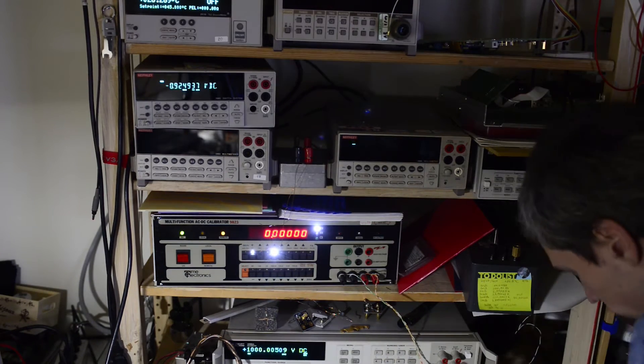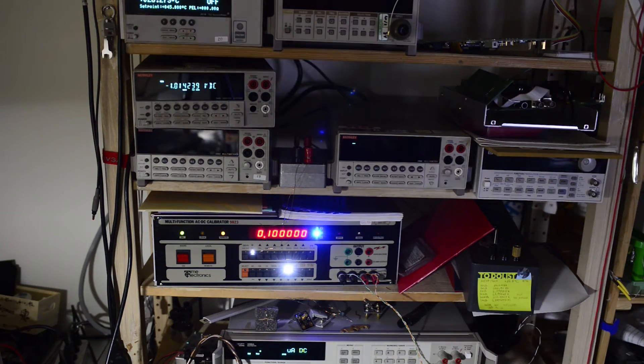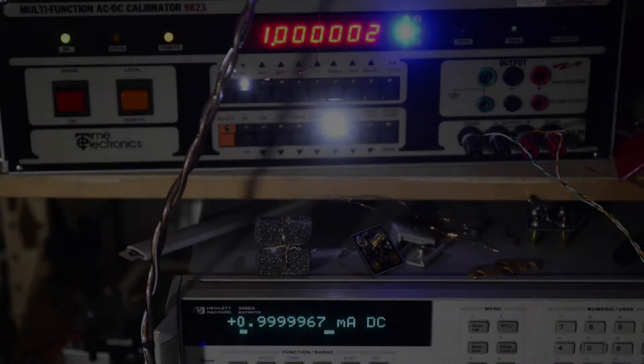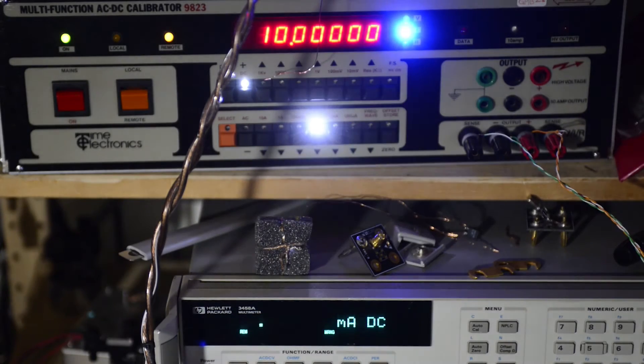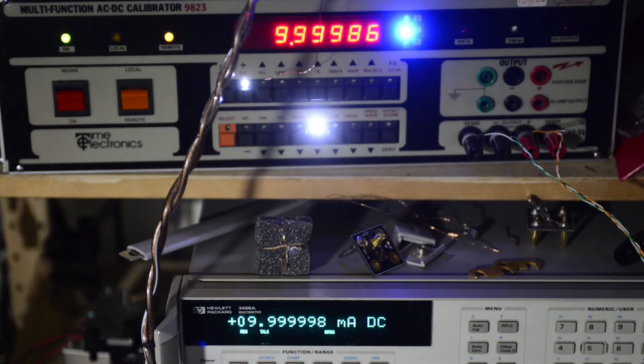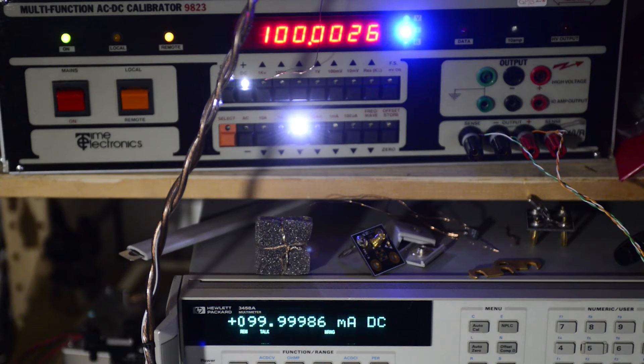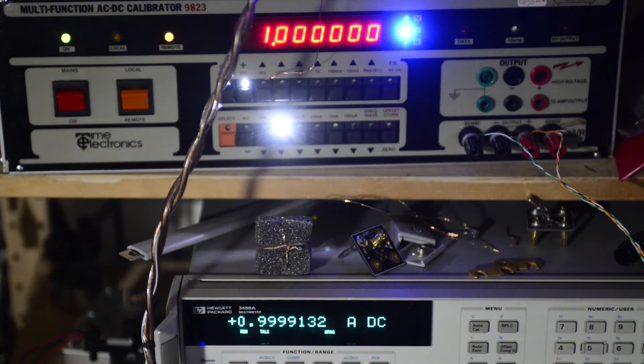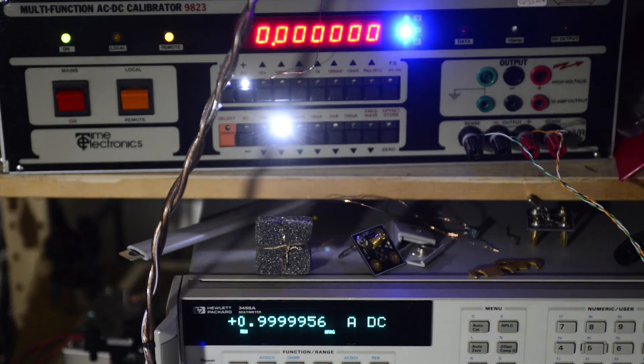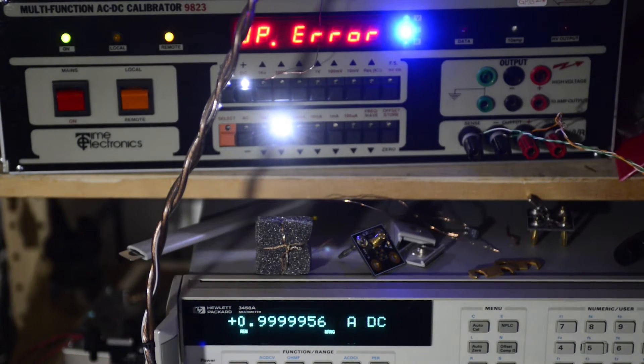Now voltage test is done and we can proceed with testing current and resistance output on the calibrator. For current and resistance I will only measure calibrator output using HP meter, and then use those measured values for model 2000 calibration.